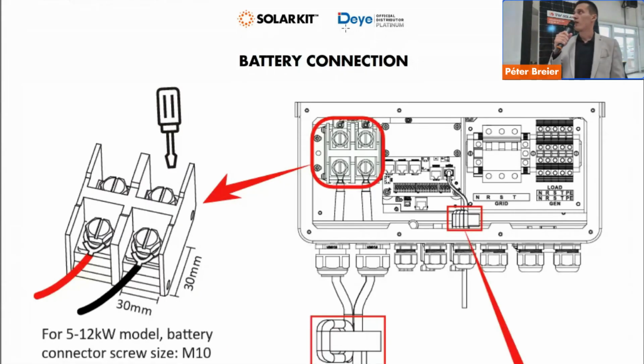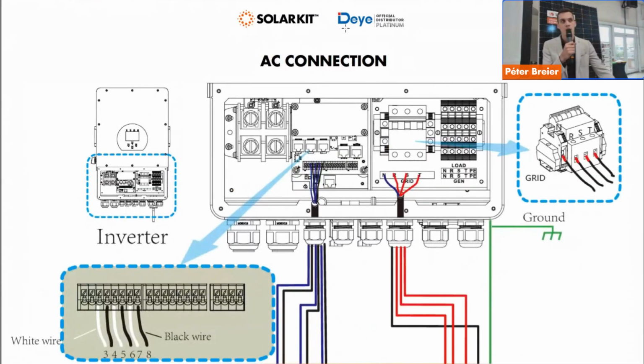Here on the left, you can find the positive and negative terminals for the battery connection. So this is what you have to use. It's the same whether you use lithium batteries or acid batteries: this is where you have to connect the batteries. From the AC side, you have three connection points: the grid, the load, and the generator. Basically, you have to use the grid most of the time, because here you can connect the power grid as a supply, and you can also inject back into the grid on that port. This is used, I believe, in like 80 or 90% of installations.